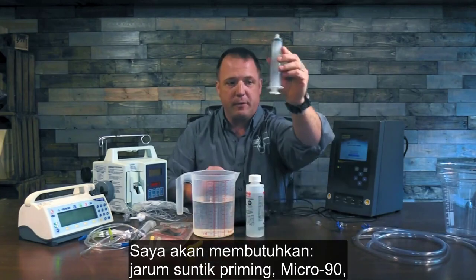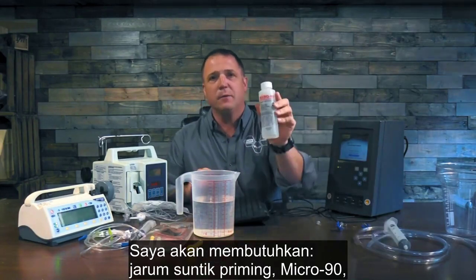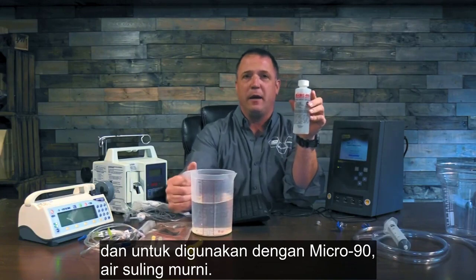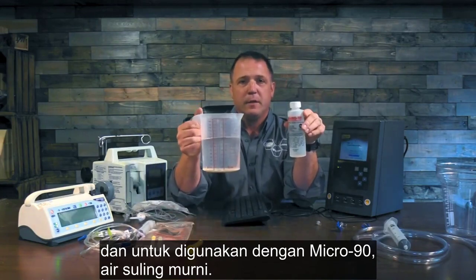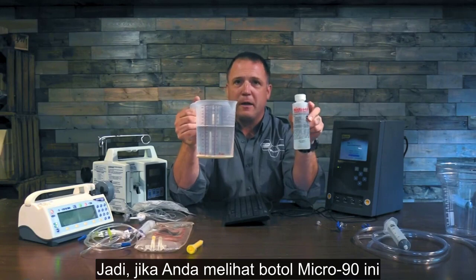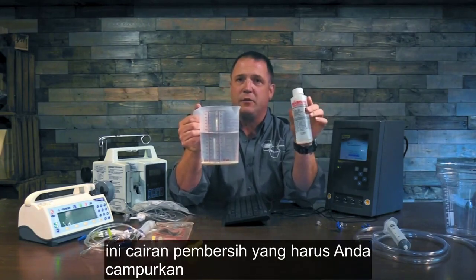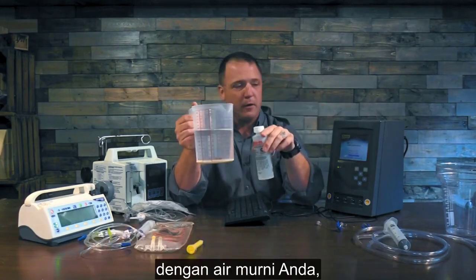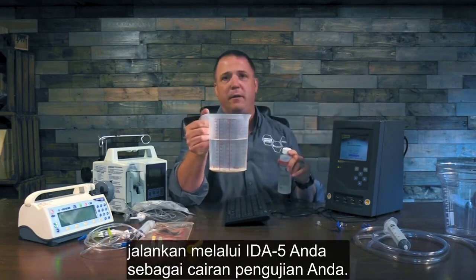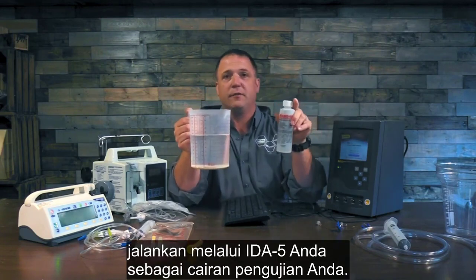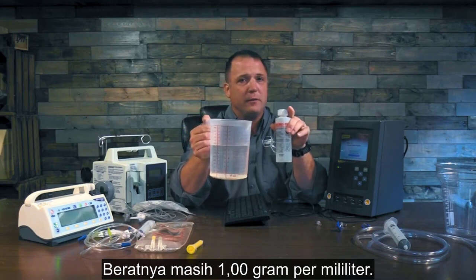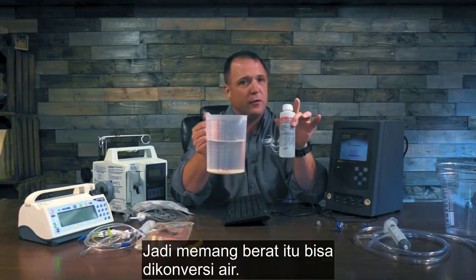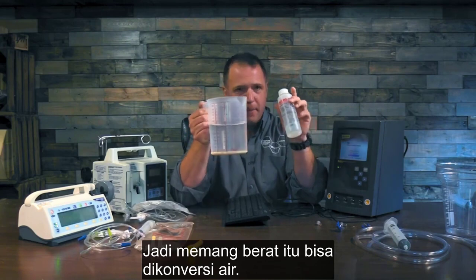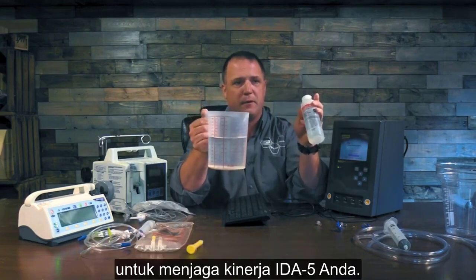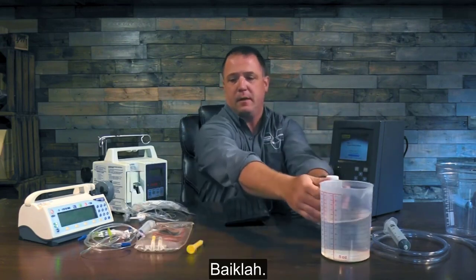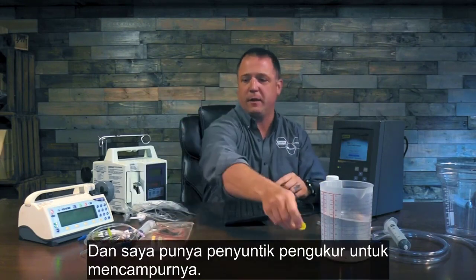I'm going to need a priming syringe, Micro 90, and to go with the Micro 90, pure distilled water. If you look at this bottle of Micro 90 that came with your IDA-5, this is a cleaning solution that you should run with your pure water. Run it through your IDA-5 as your test solution. It still weighs 1.00 grams per milliliter, so it does do that weight to water conversion. But this is a great way to keep the life of your IDA-5 up. All right, and I have a little measuring syringe to mix that up.